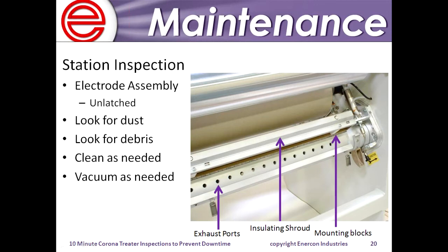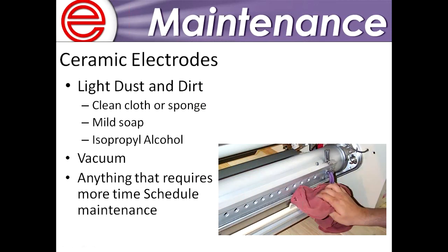One thing that we might want to do, if you do have some buildup, if there's any material like that there, is take a shop vac to vacuum out that area, or you can use oil-free compressed air to blow out any debris and get as much out of that area as possible to keep it as clean as possible. And again, this outlines what we were mentioning as far as cleaning that out. Just lint-free rag, isopropyl alcohol. You can use mild soap, but again, always make sure you follow it up with an isopropyl alcohol rinse.